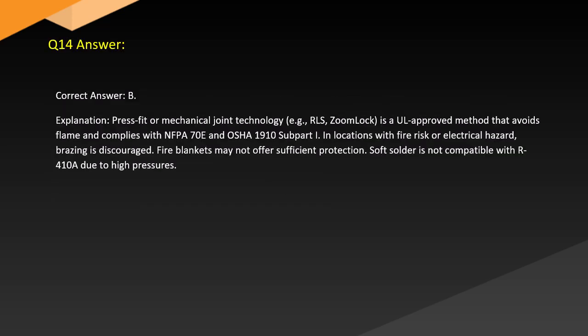Answer. Correct answer: B. Explanation. Press-fit or mechanical joint technology, such as RLS zoom lock, is an approved method that avoids flame and complies with NFPA 70E and OSHA 1910 Subpart I. In locations with fire risk or electrical hazard, brazing is discouraged. Fire blankets may not offer sufficient protection. Soft solder is not compatible with R-410A due to high pressures.